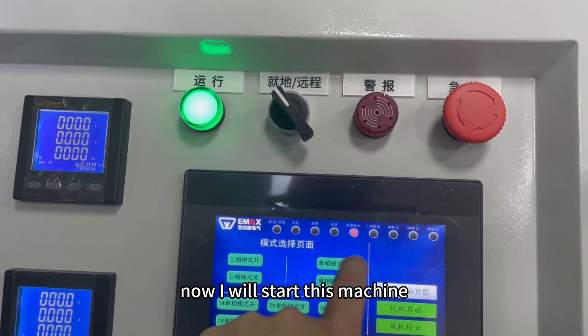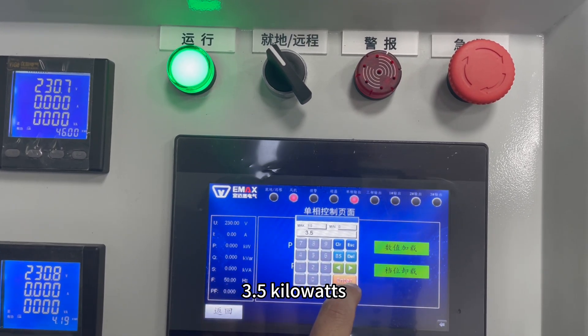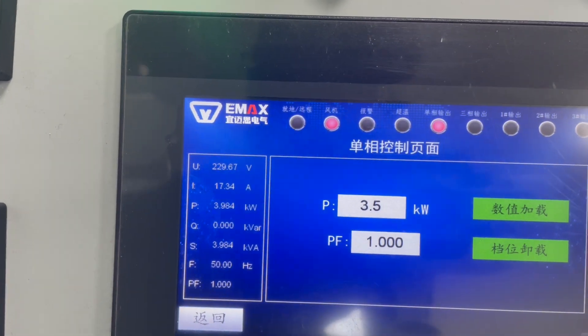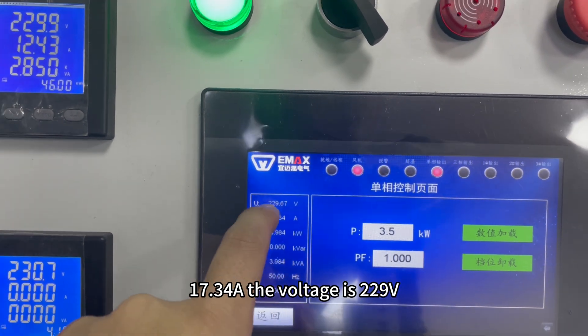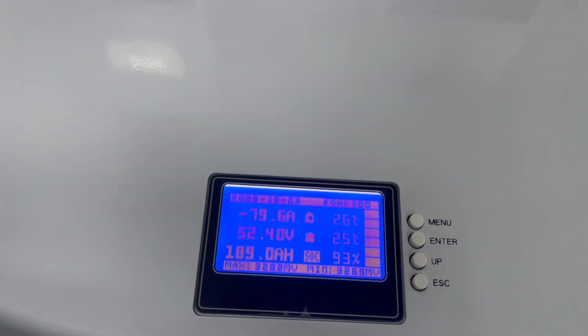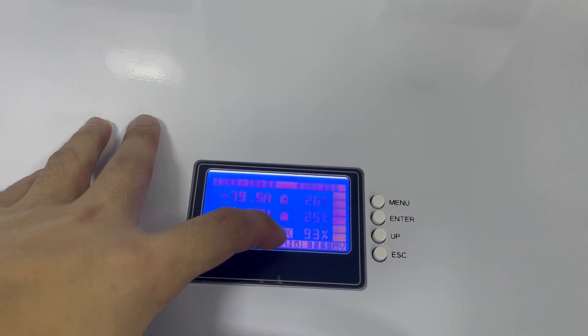Now I will start this machine. I will use 3.5kW of power for testing. The load starts — the power is 3.9kW and the current is 17.34A. The voltage is 229V. We can check that the battery output current is 79.6A and the capacity is 93%.